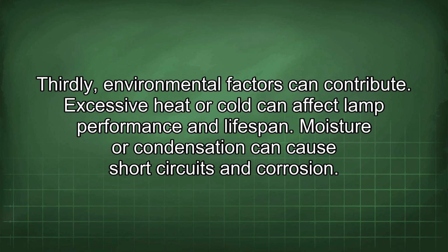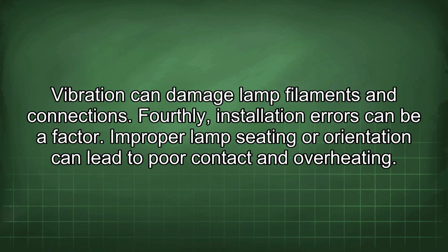Excessive heat or cold can affect lamp performance and lifespan. Moisture or condensation can cause short circuits and corrosion. Vibration can damage lamp filaments and connections. Fourthly, installation errors can be a factor.